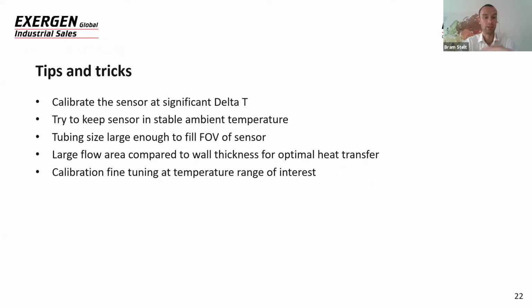Some tips and tricks on using this technology and doing the calibration. First of all, as Bob explained, the millivolt signal that the sensor generates is based on the delta T, the difference between the target temperature and the sensor temperature. If there is no delta T, there is 0 millivolt. And if you then adjust the set screw, nothing will happen. So you need a certain delta T for the calibration to work.